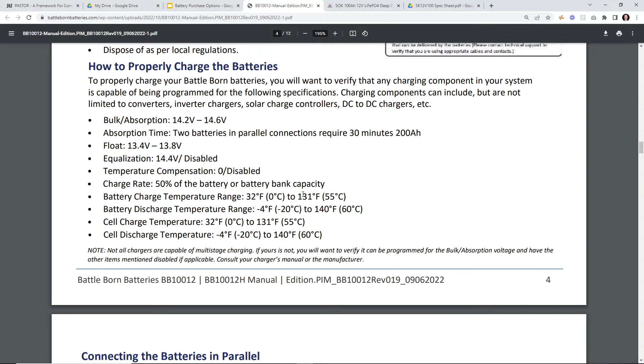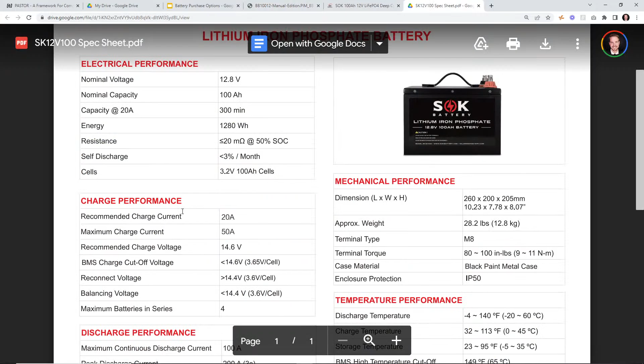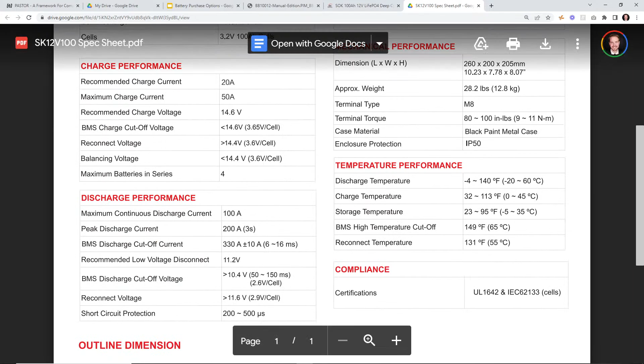This right here is explaining how you can take the 12 volt 200 amp hour bank. This is the same example I was giving you guys: how you can continuously run 200 amps for 30 seconds, or in a situation, do 400 amps for 30 seconds. So when we were talking about the peak discharge current, this 200 amps, typically it's going to be twice the amount of the amp hours for a short burst. So say you're turning on your inverter, there's going to be a surge of current to kick on that inverter. The surge should not last longer than a couple of seconds.